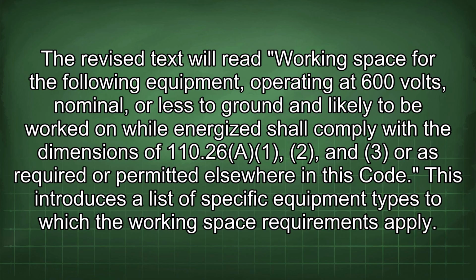The revised text will read: "Working space for the following equipment operating at 600 volts, nominal or less to ground, and likely to be worked on while energized, shall comply with the dimensions of 110.26(A)(1), (2), and (3), or as required or permitted elsewhere in this code." This introduces a list of specific equipment types to which the working space requirements apply.